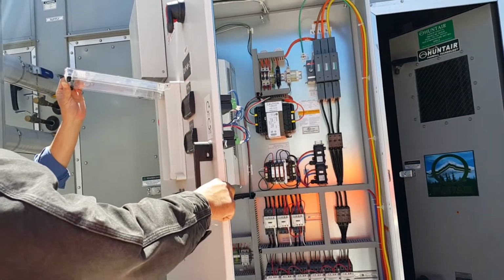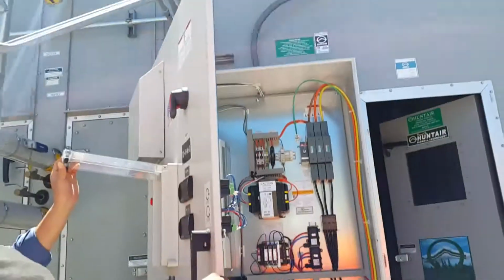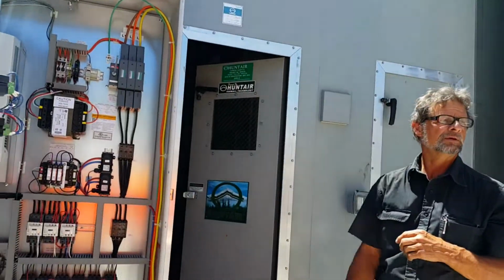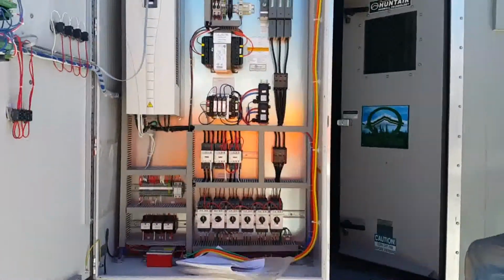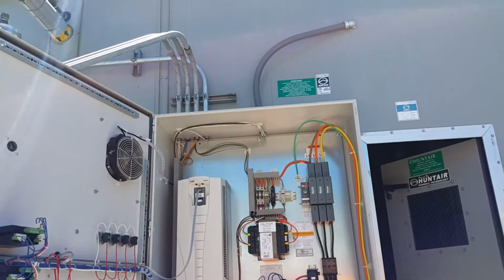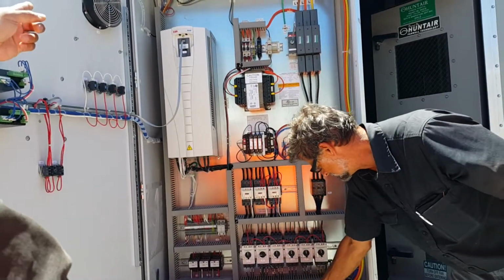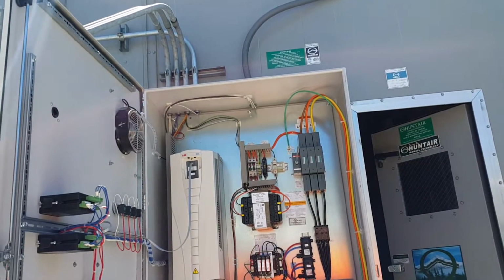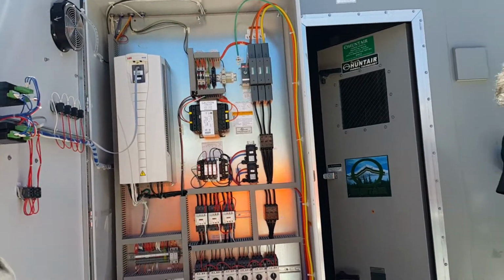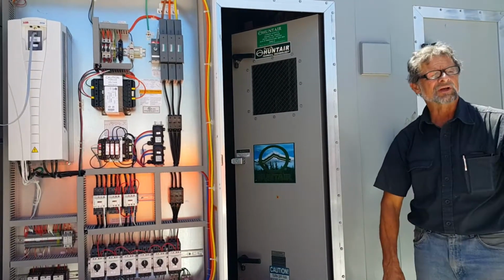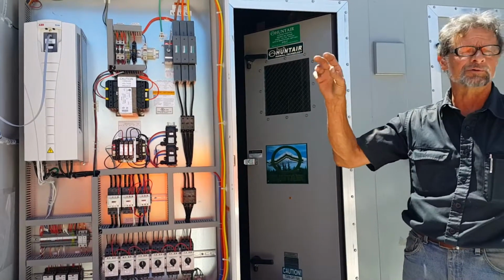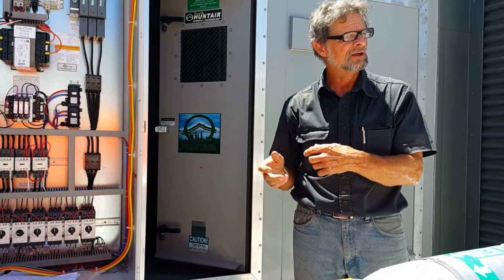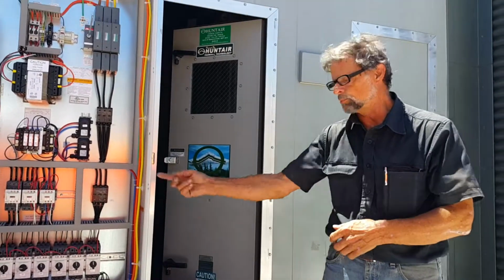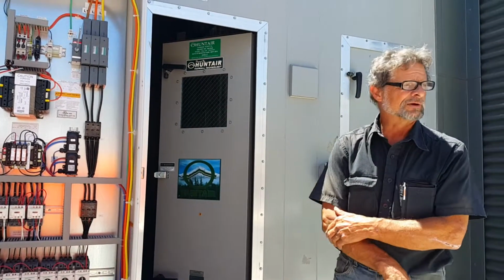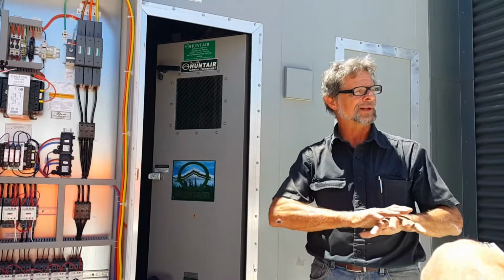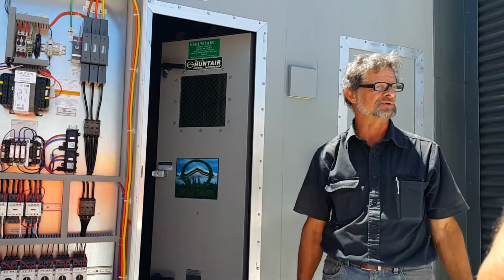Actually on the other side of the coil, so in this case, since you have hot and chilled water flow, it should be coming from prior to the hot water. To keep it cool. The unit was designed so that the hot water coil was just supposed to take the chill off the outside air. And now we're supposed to go with 70 degrees. So I said, okay, we can plug that in there. The general contractor decided a good way to dry out the recarpeting of the building would be to take that temperature way out.